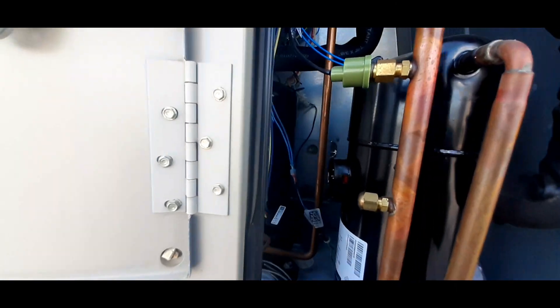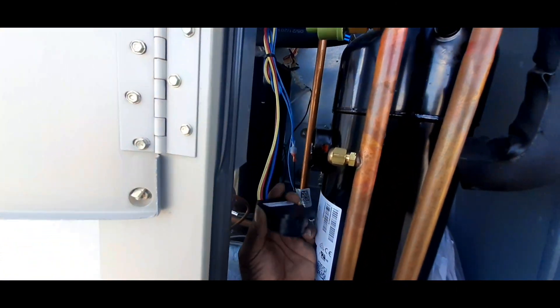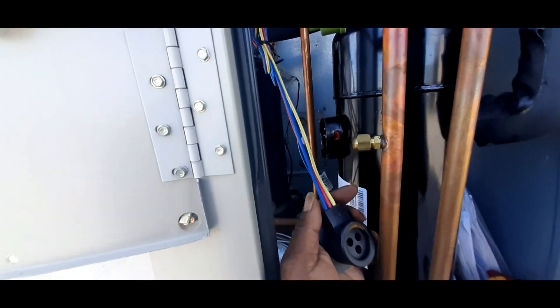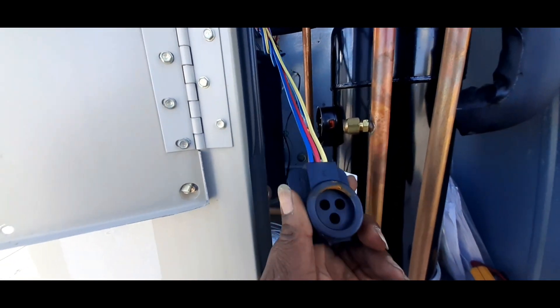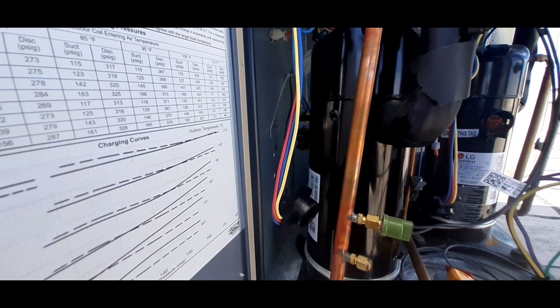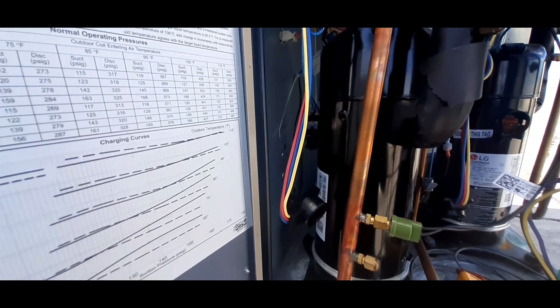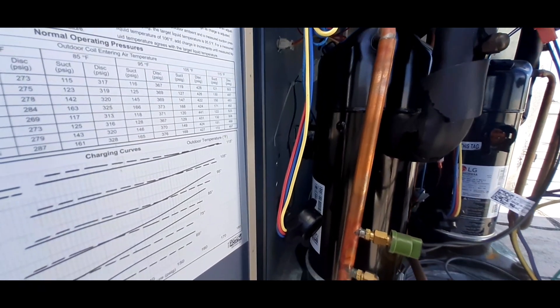All right, so I just ohmed out this compressor. Everything checked out fine, also checked out these wires heading back and these checked out also. Just check the next. All right, so I just checked this compressor for continuity to ground, checking for shorts, also check the windings to make sure that they're reading the same. All three terminals should be within the same range.